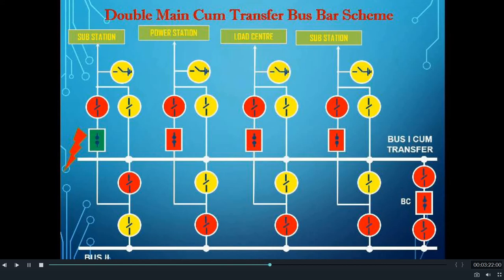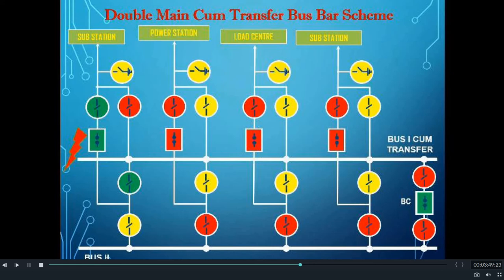As the circuit breaker is faulty, the faulty circuit breaker must be isolated. For isolating the faulty circuit breaker, we will open the isolators on either side of the circuit breaker manually. For connecting the feeder to the system, we will close manually the transfer isolator of the feeder. That transfer isolator will connect the feeder to bus number 1, which will now act as the transfer bus. We will then close the transfer bus coupler, connecting the feeder to the system through bus number 1, which is now acting as the transfer bus, connected to the main bus through the transfer bus coupler. Hence, the substation bus bar will act as a main and transfer bus bar system.